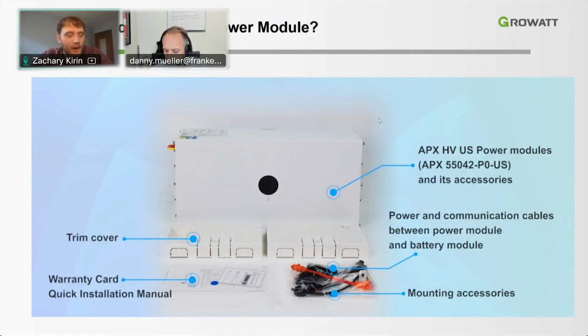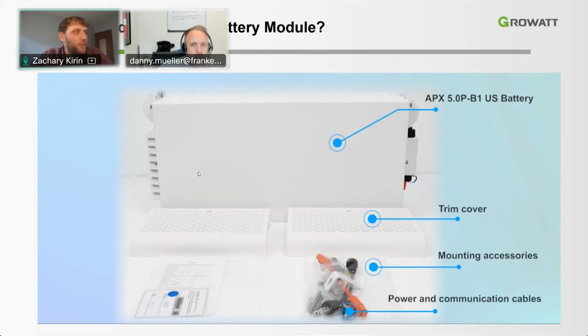As for what is included with the power module, you will of course get the power module and its accessories, the power and communication cables to run between each battery, the mounting accessories for each of the battery modules, and the warranty card. The installation manual will be with it, and I recommend giving that a read before you attempt the installation. So what is included with the battery module? You'll notice that the power module and the battery module come with these trim covers. This is to make the battery look really nice after the installation is complete. The APX 5 kilowatt hour battery will be included, and power communication cables between each battery pack.